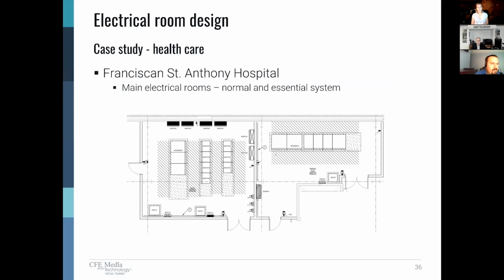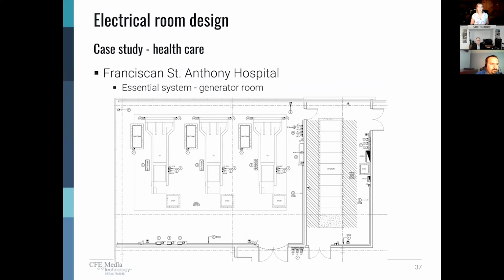So this is an example of the main electrical room. So we had the main electrical room and the main essential system electrical room. You can see that we had them separated. The automatic transfer switch equipment being in the essential side, and then the incoming electrical services on the normal side. So we kept separation, and this was located on the lowest level of the building. And then, like I mentioned previously, we had 3 generators on the project that are co-located within the generator room. We had the 3-hour fire rating around this room, and then adjacent to that, we had paralleling gear for the building, which required both front and rear access.